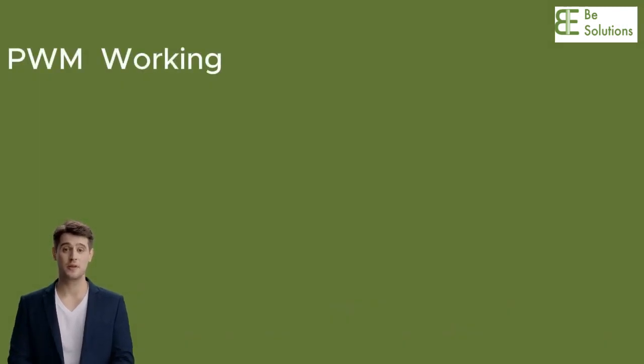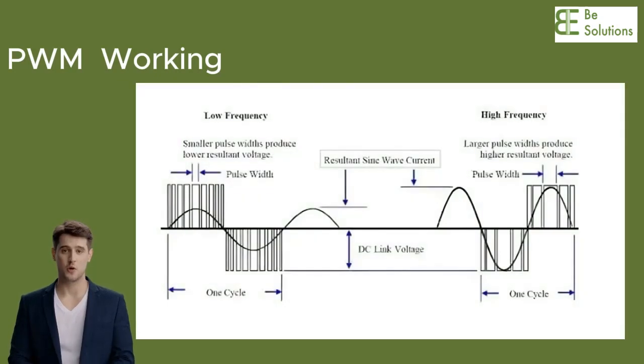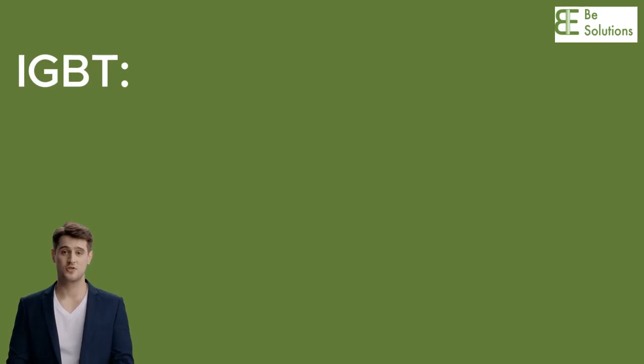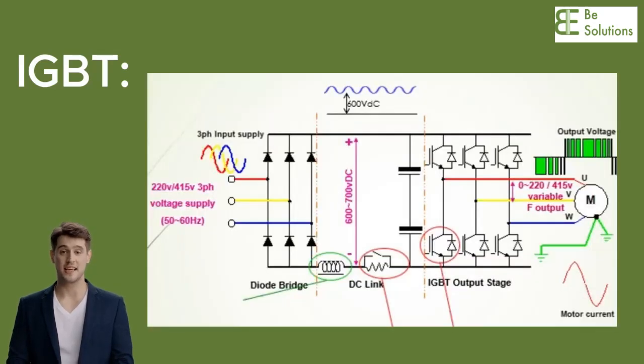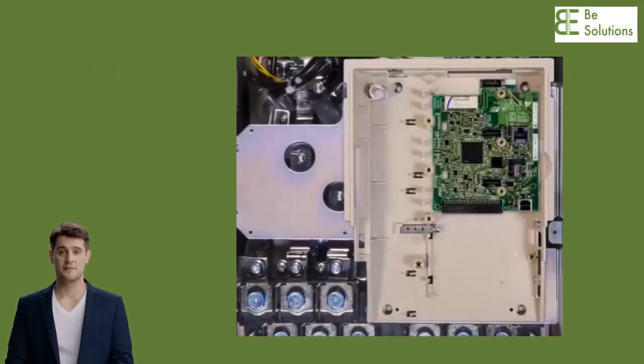Now let's study how PWM helps in maintaining V/F ratio constant. In the diagram we can see that as the frequency increases, the PWM increases the peak of the sine wave by modulating the width of the pulse, in other words, the duration for which the IGBT allows the power to flow. The duration of the pulse affects the voltage. The IGBT gate trigger card drives the IGBT gates, and hence power flows through the IGBTs, resulting in a pulse width modulated wave that approximates a sine wave.